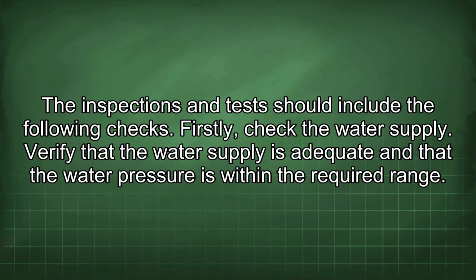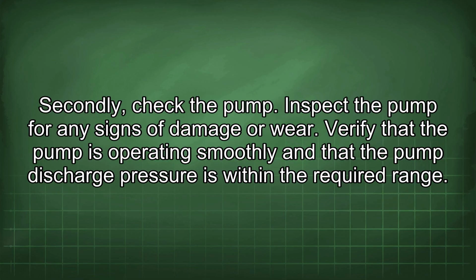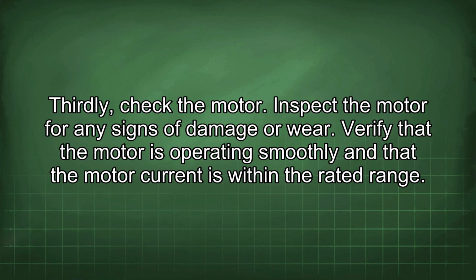Firstly, check the water supply. Verify that the water supply is adequate and that the water pressure is within the required range. Secondly, check the pump. Inspect the pump for any signs of damage or wear. Verify that the pump is operating smoothly and that the pump discharge pressure is within the required range. Thirdly, check the motor. Inspect the motor for any signs of damage or wear. Verify that the motor is operating smoothly and that the motor current is within the rated range.